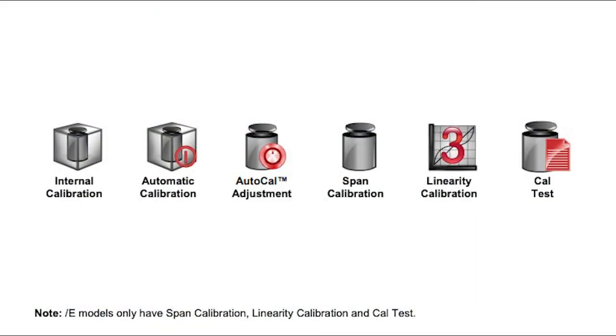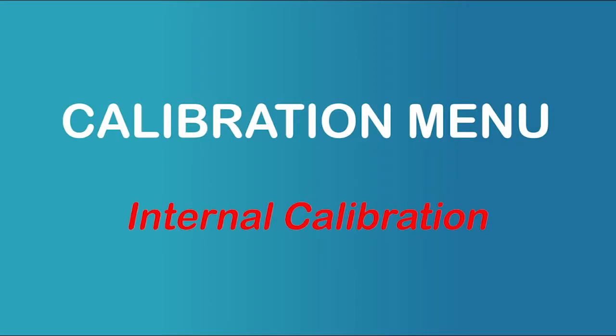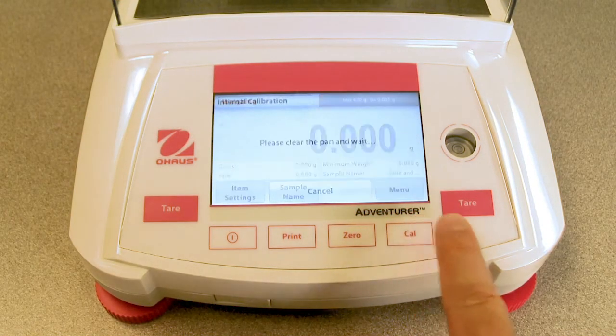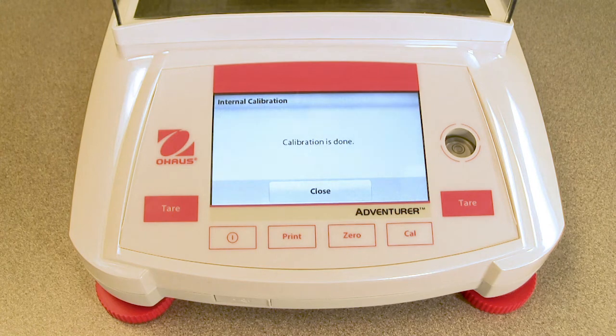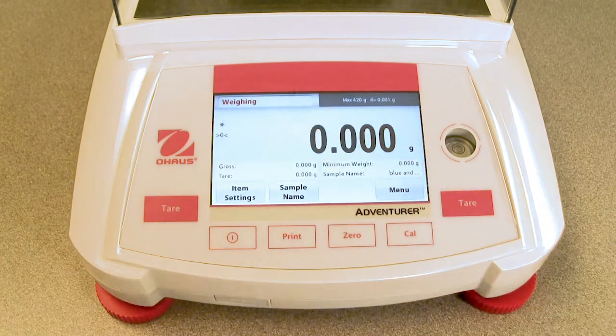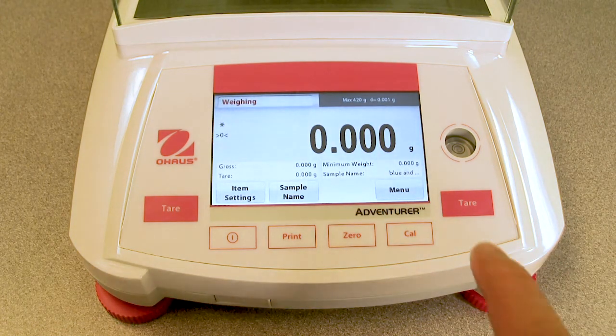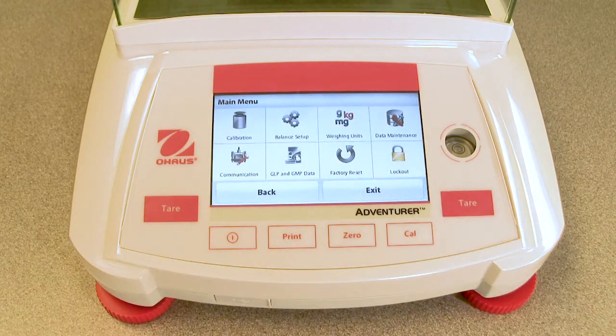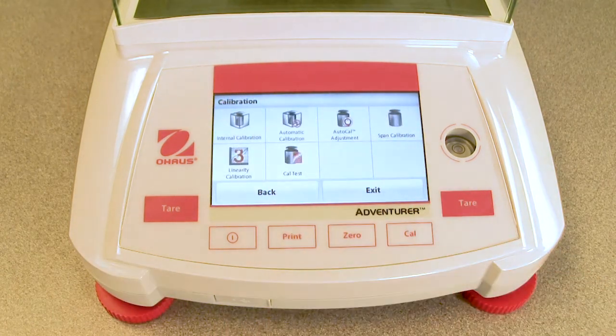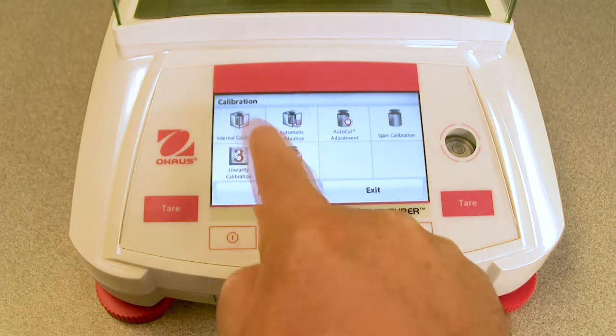Adventurer balances InCal models offer a choice of 6 calibration methods: internal calibration, automatic calibration, AutoCal adjustment, span calibration, linearity calibration, and CAL test calibration. Internal calibration is accomplished with the internal calibration mass. Internal calibration can be performed at any time, provided the balance has been warmed up to operating temperature and is level. With no load on the pan, touch internal calibration.